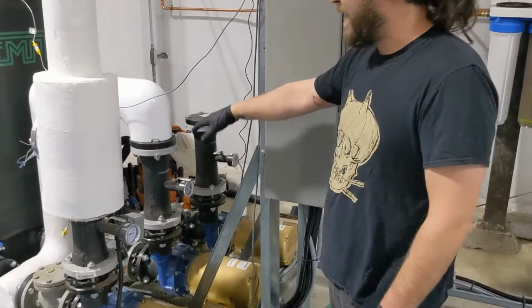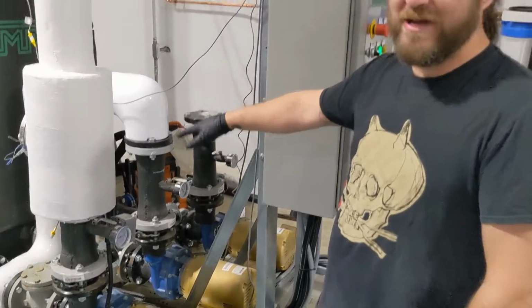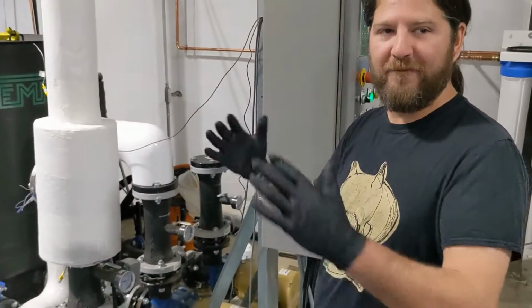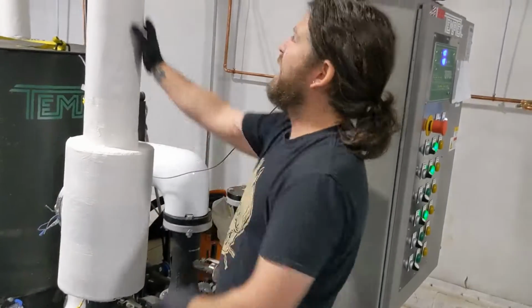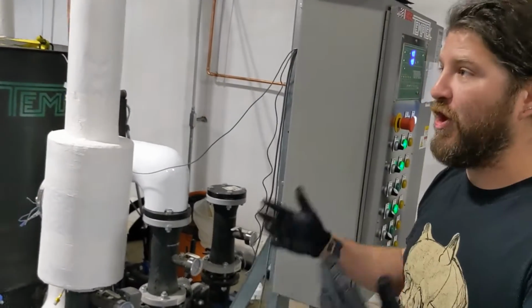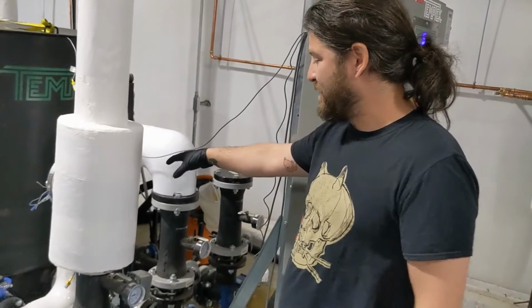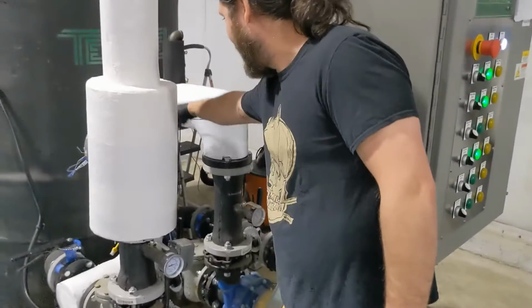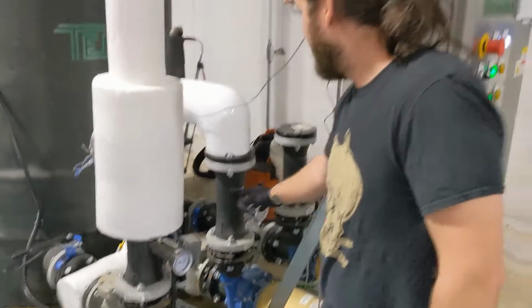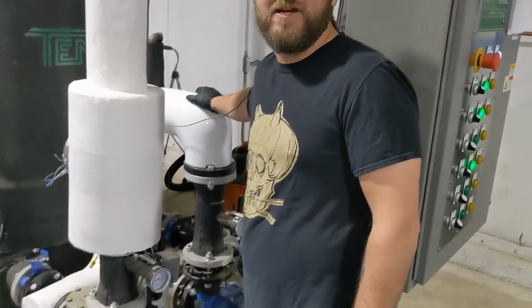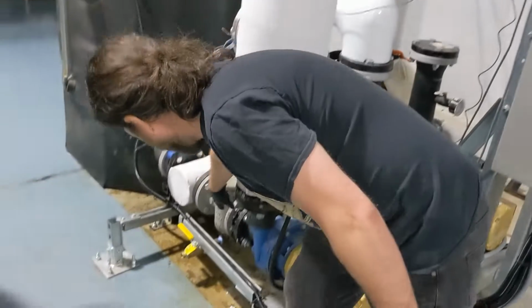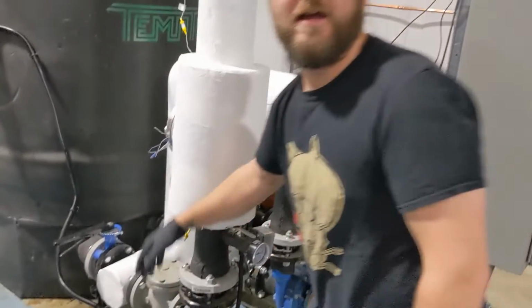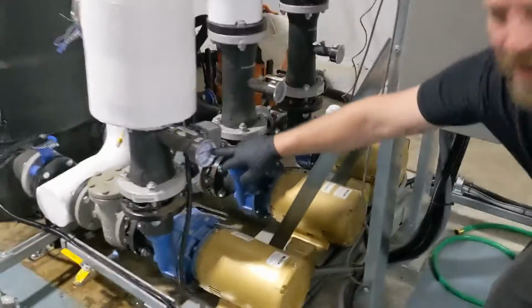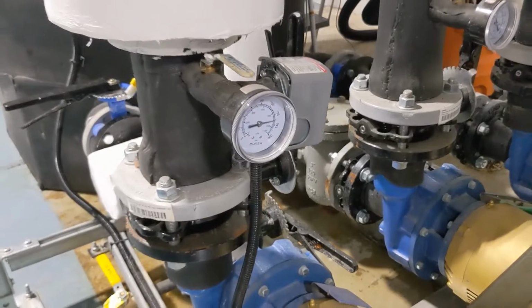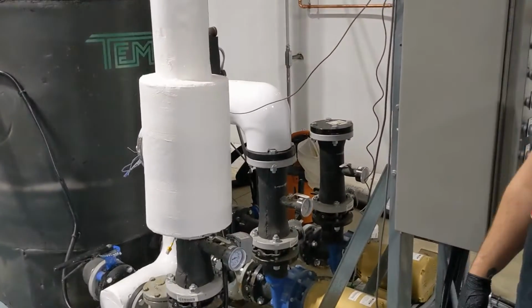Because we have these extra ones, there are 2 different ways to tie pumps together. You can manifold them together, taking these 2 and having them go up in one pipe, which increases your flow, but it won't increase your pressure. So we ran them in series, which is the other way. We come out that center pipe from the tank into this pump, and then it discharges into this one at 70 PSI. So when it comes around and hits the 0 point on this pump, it thinks it's at 0, but it's actually at 70. So when it comes out, you can see we're at 130 PSI right here, which puts us where we need to be. So you made it work. We made it work.